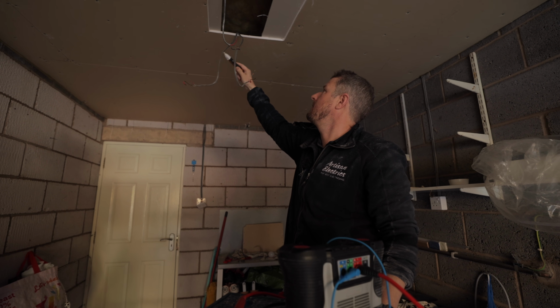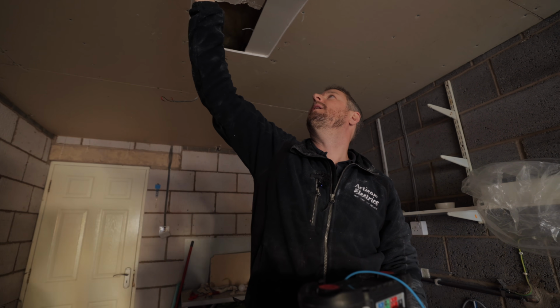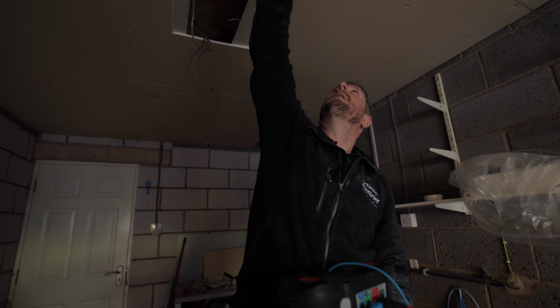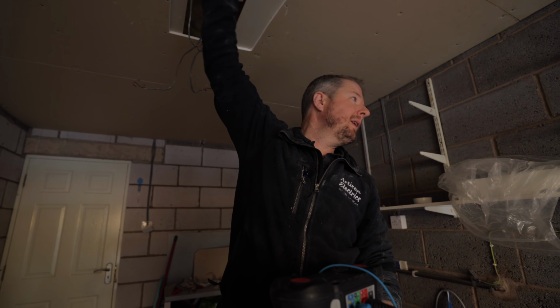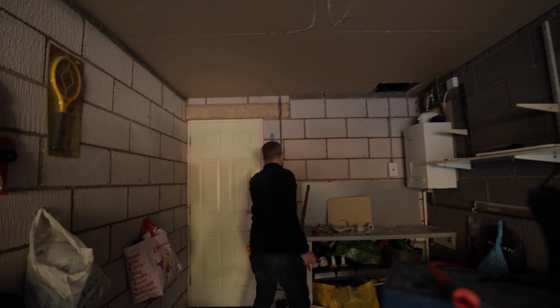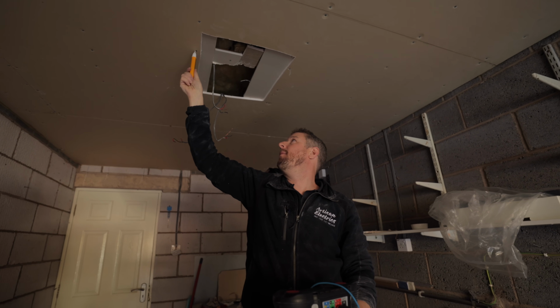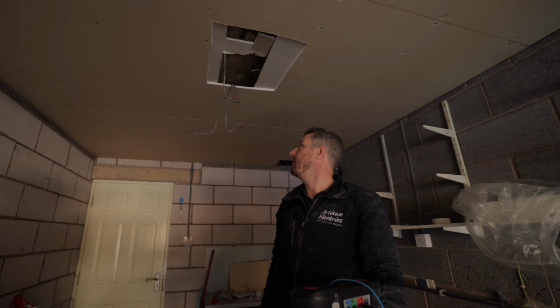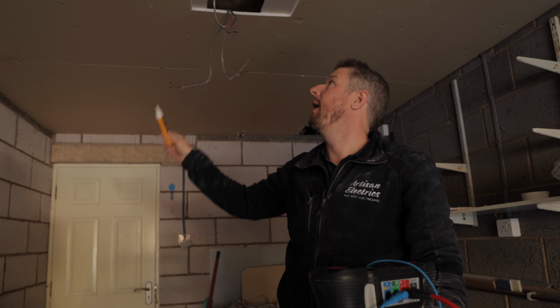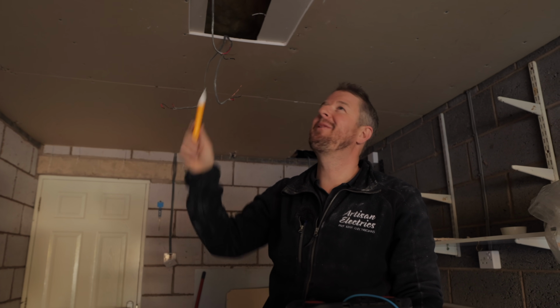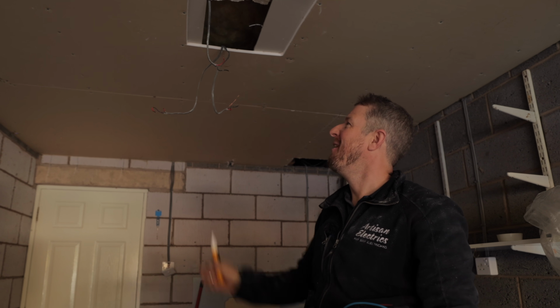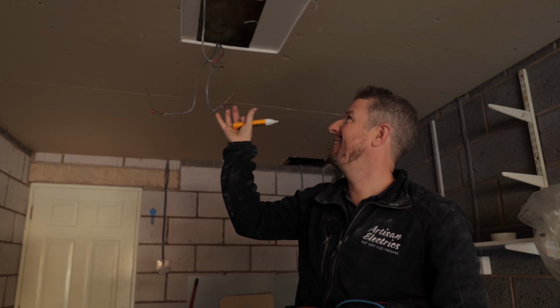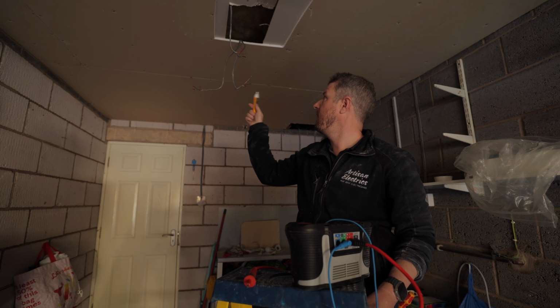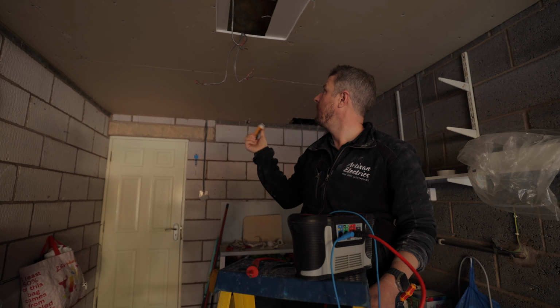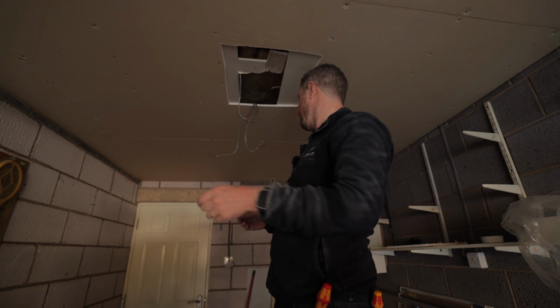These are dead, which they should be. And now we've got no issues. We're making progress. We have somehow managed to eliminate the problem. But what have we done to eliminate it? We've removed the pendant, the light fitting. Those 3 lives were connected together. We separated them out. So we've turned the breaker off again.